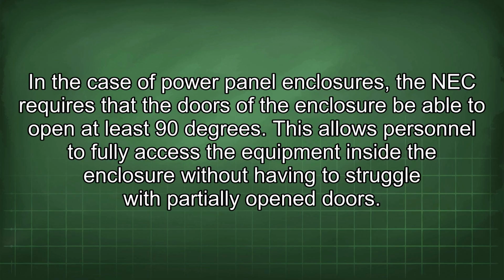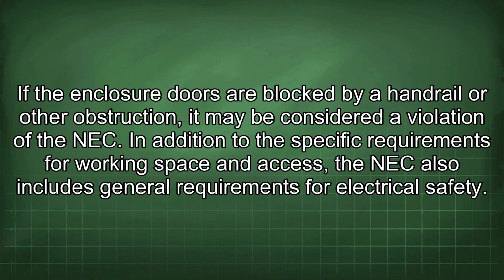In the case of power panel enclosures, the NEC requires that the doors of the enclosure be able to open at least 90 degrees. This allows personnel to fully access the equipment inside the enclosure without having to struggle with partially open doors. If the enclosure doors are blocked by a handrail or other obstruction, it may be considered a violation of the NEC.